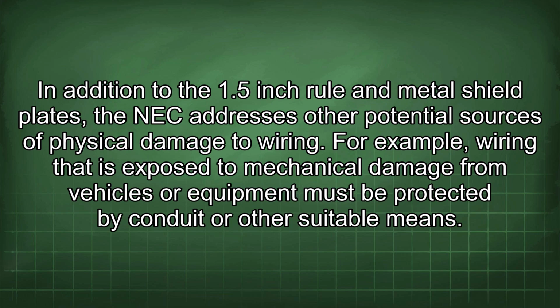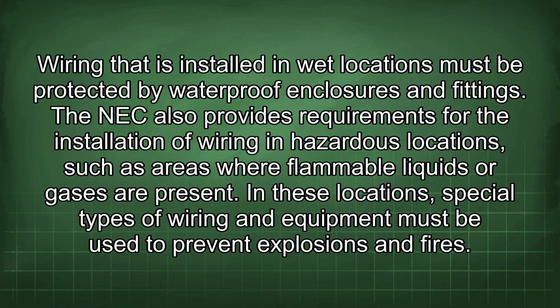In addition to the 1.5-inch rule and metal shield plates, the NEC addresses other potential sources of physical damage to wiring. For example, wiring exposed to mechanical damage from vehicles or equipment must be protected by conduit or other suitable means. Wiring installed in wet locations must be protected by waterproof enclosures and fittings. The NEC also provides requirements for the installation of wiring in hazardous locations, such as areas where flammable liquids or gases are present. In these locations, special types of wiring and equipment must be used to prevent explosions and fires.